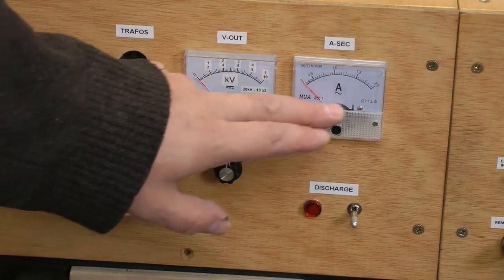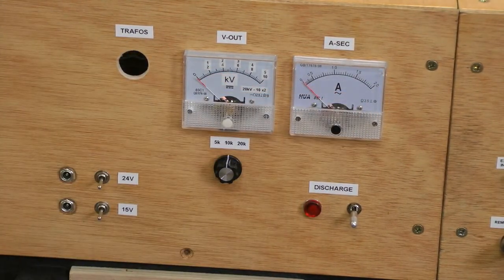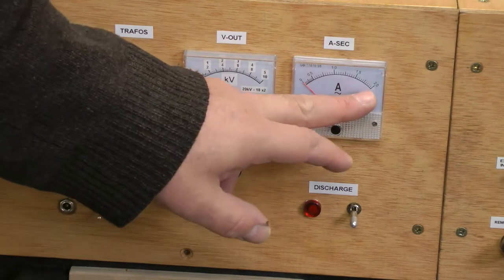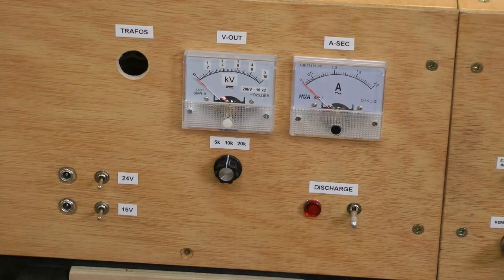Very rare that you run it up to that. You can put a 0 to 3 amp meter in there to cover its full range of output, but I rarely run it up anywhere near that point. So 0 to 2 amps is fine on the secondary circuit. There is then the output circuit, so in kilovolts.